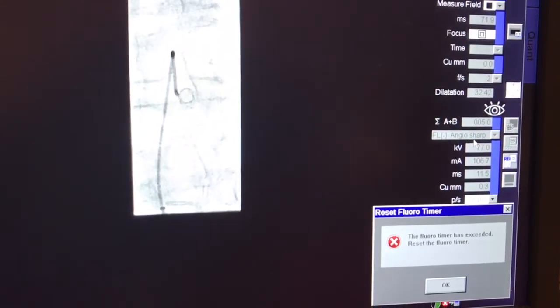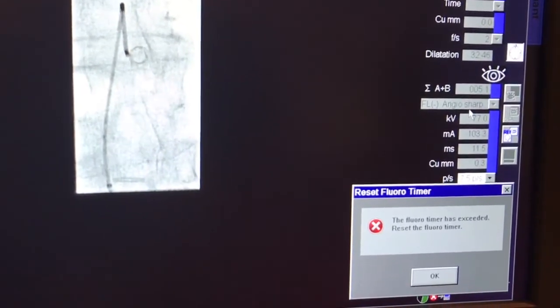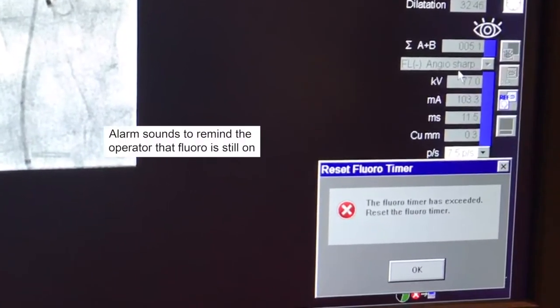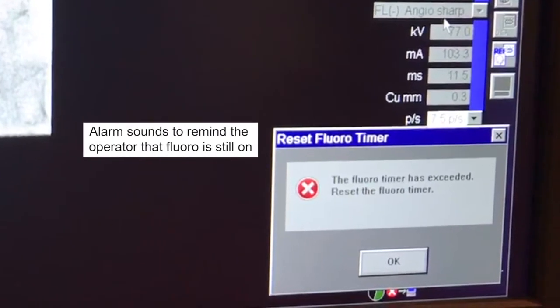Fluoroscopes have an audible alarm that will sound after the total beam on time has exceeded a set threshold. You can continue using the fluoroscope after the alarm sounds. It just serves as a reminder to the operator.